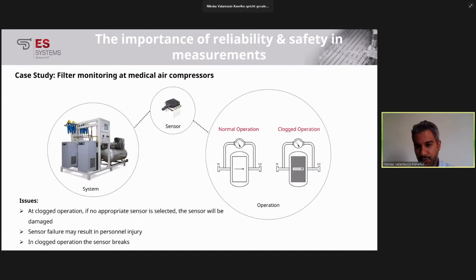As the equipment works over time, the filters get dirty and clogged. So manufacturers, in order to measure the cleanliness of the filters, apply a differential pressure sensor across the filter at the input and output. By measuring the differential pressure, they can see the condition of the filter - whether it's clean and still operational, or getting clogged, which means the differential pressure increases due to dust and oil particles trapped in the filter, meaning the filter will need replacement.